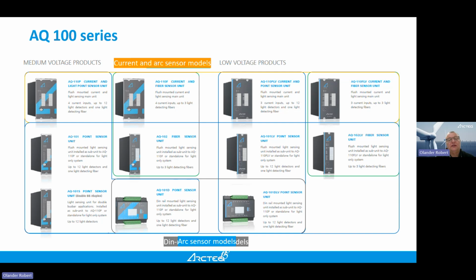But they can also work standalone. So it depends again on the specification. Sometimes it's specified that you need two criteria, sometimes it's not, and then a current only system or light only system is often used. The only thing, when you have a light only system, is that you need to be careful that people are not allowed to use cameras or things like that in the area. There are DIN rail installation models or flush mounted, depending on what type of installation you need.